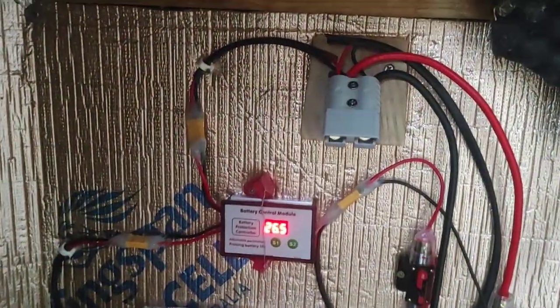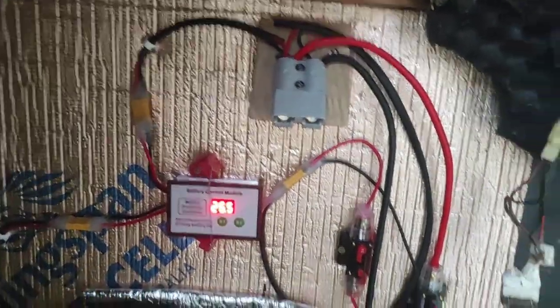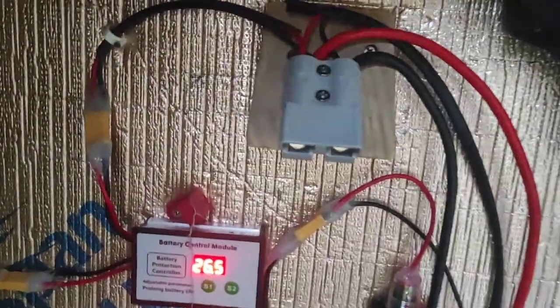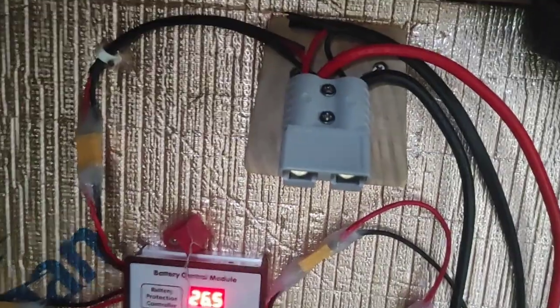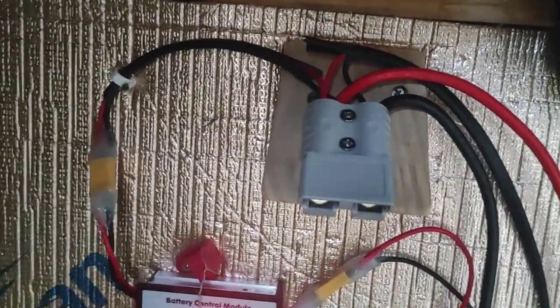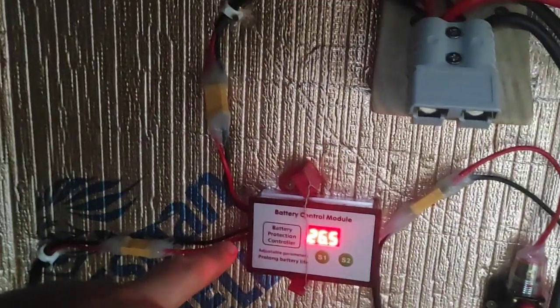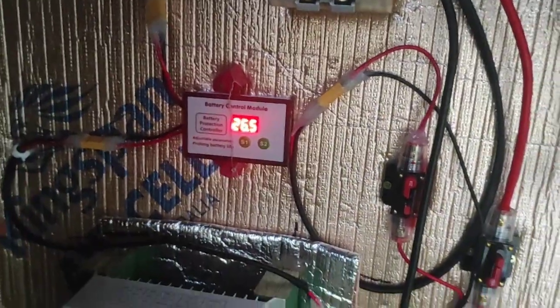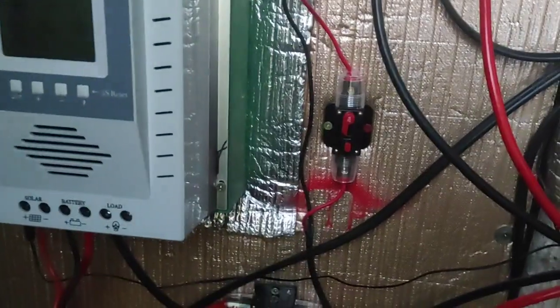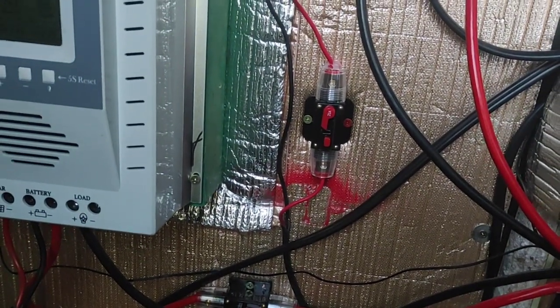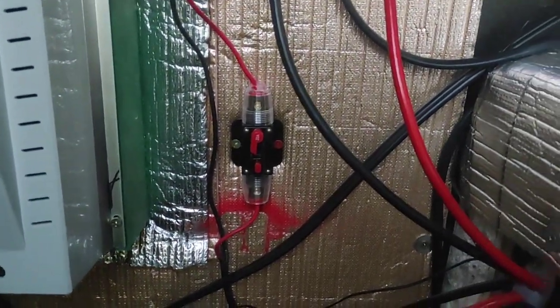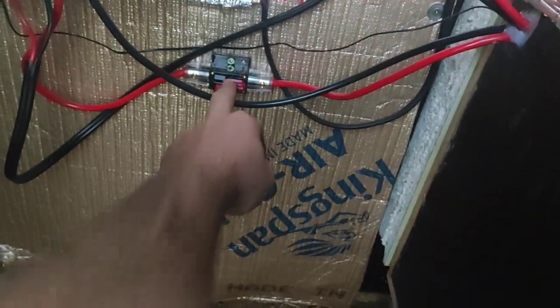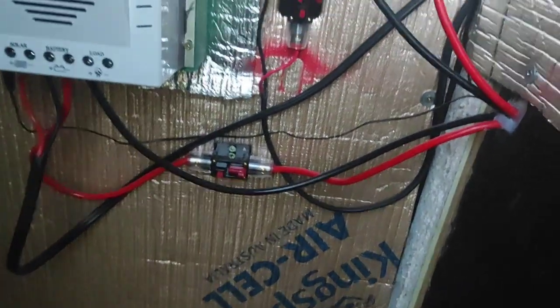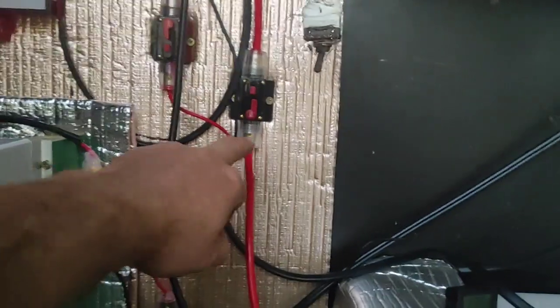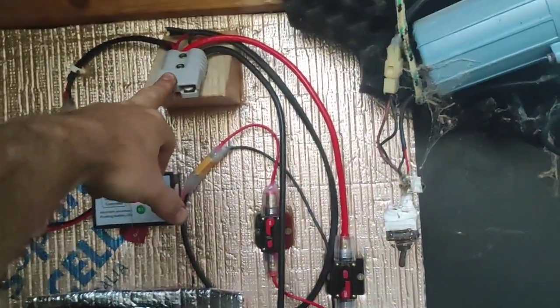Forgot to mention that Anderson plug there, that's a 120 amp Anderson plug, and that's where I plug in the inverter if I ever get a brownout and need 240 volt power. I've piggybacked the low voltage cutoff device off there, and that is also on a 20 amp breaker, so that'll cut out. All the run coming from the battery has a 100 amp breaker, and the same 100 amp breaker runs to the Anderson, so the 100 amp cable is protected from melting itself to pieces.